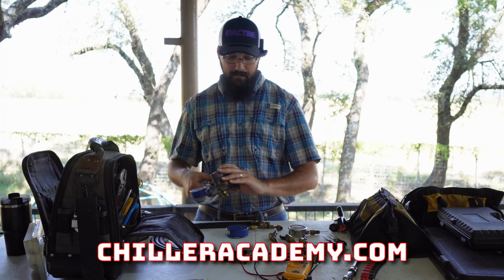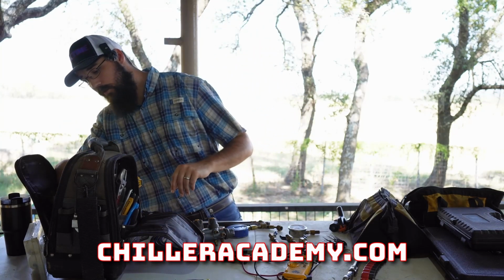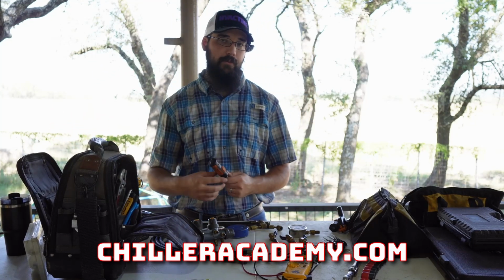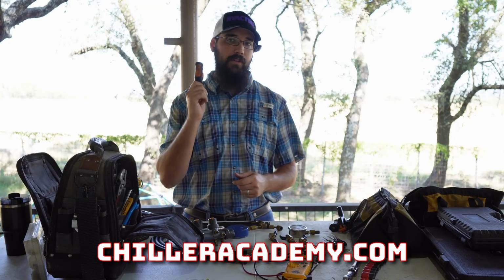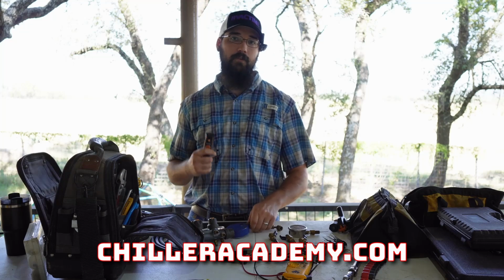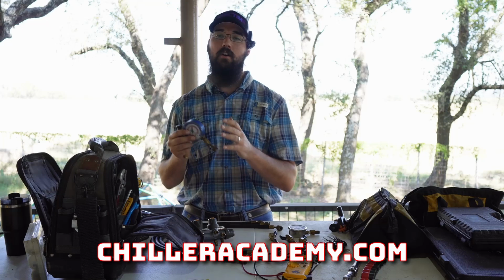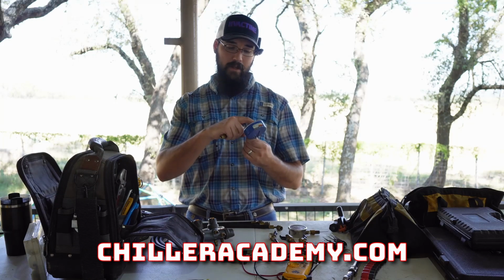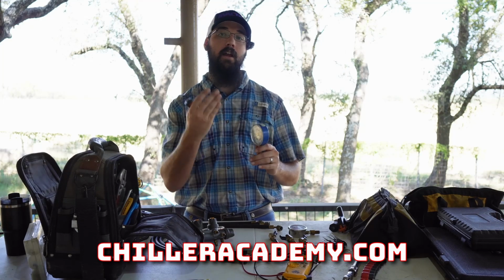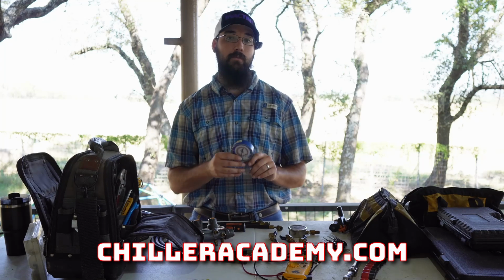That's perfectly fine. Now, one thing to keep in mind with digital or Bluetooth: while digital on the manifold is a faster readout than Bluetooth, both have some lag and delay. If you're doing really precise differential pressure testing on safety switches, you may not actually see the actual trigger point. It may be a couple of PSI below that, because these gauges did not update fast enough compared to what the actual mechanical switch will see.